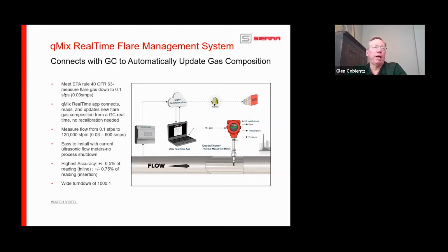But when you're dealing with main flares at refineries, main flares at chemical plants, this is something that is going to be needed to supplement the multipath ultrasonic, or we even have a couple discussions going on right now where they're looking at this as the main flow measurement for the main flare. So just to give you an idea where we are price point wise is, depending on the final configuration of the 640S, plan on about $50,000 per point. And that includes the engineering team coming out and making sure that everything works at startup. So there's a lot of hand holding going on right when these go into the pipe, get all wired up, you start the flare up, and then away you go.